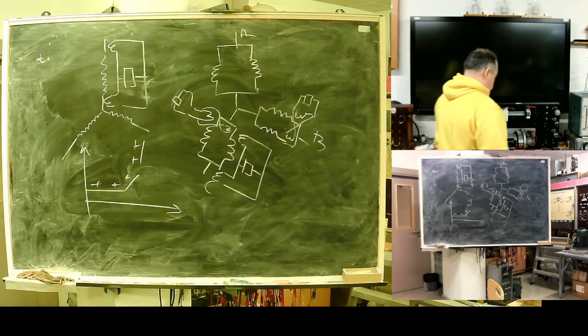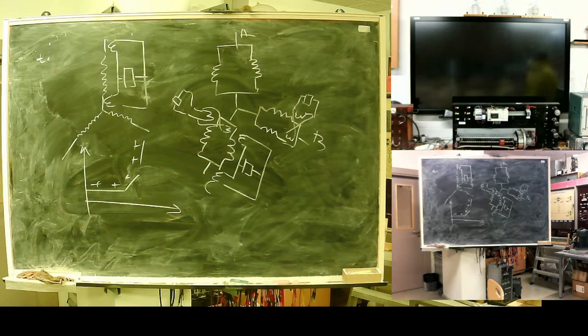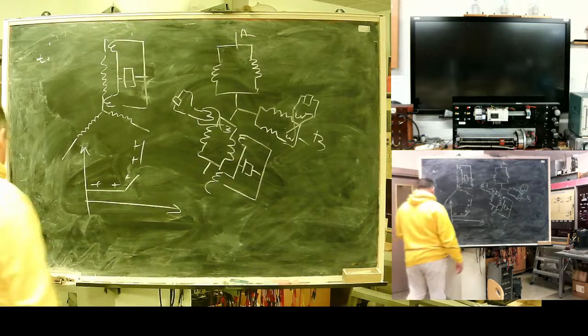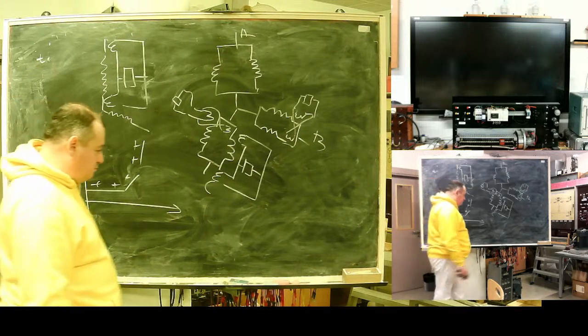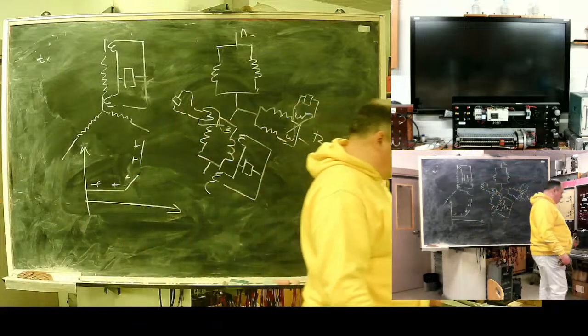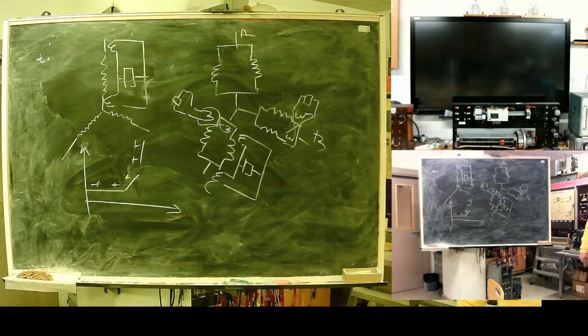Really around a multi-megawatt class generator, you will have around 12 parallel pilot wire or differential protection branches.